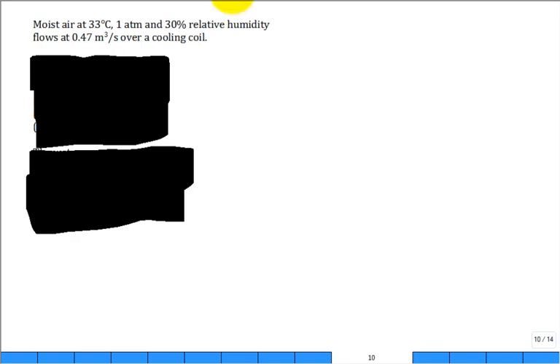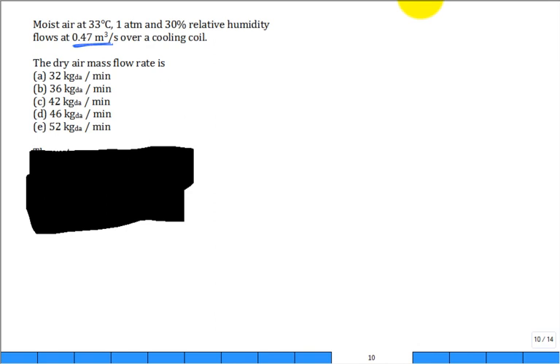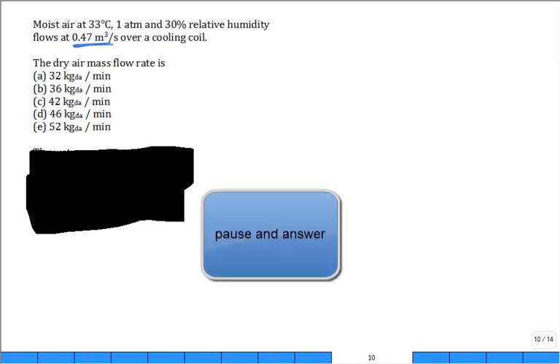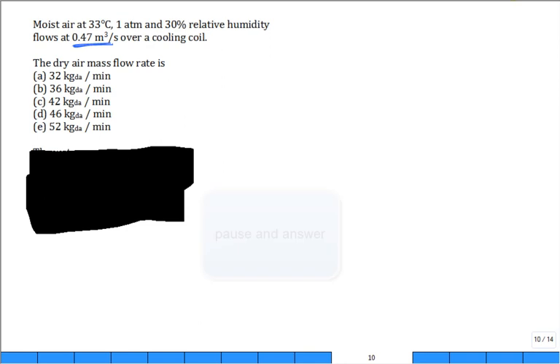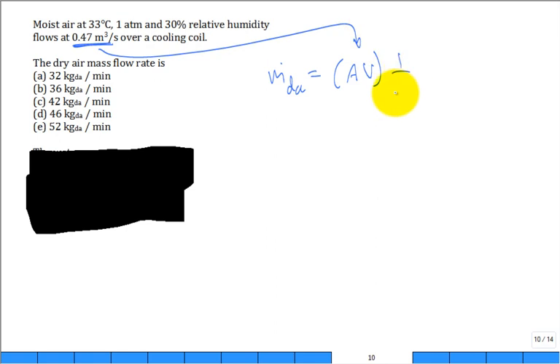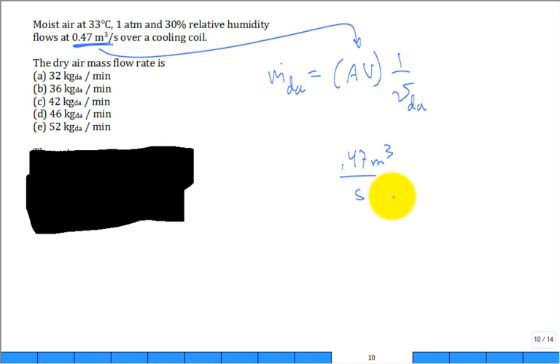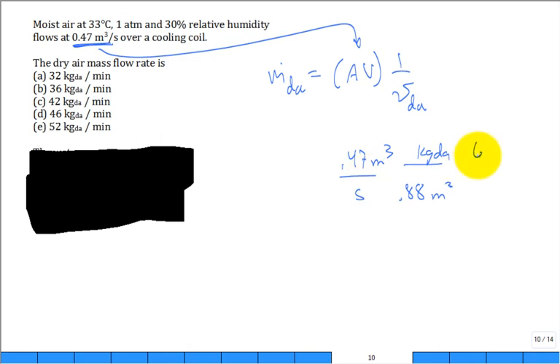Same state, but now we have a volumetric flow rate coming into the cooling coil — that's the inlet, 0.47 m³/s. Can you calculate the dry air mass flow rate? Do you multiply or divide by specific volume? You divide. So 0.47 m³/s divided by 0.888 m³/kg dry air, converted to minutes (×60), gives 32 kg dry air per minute.